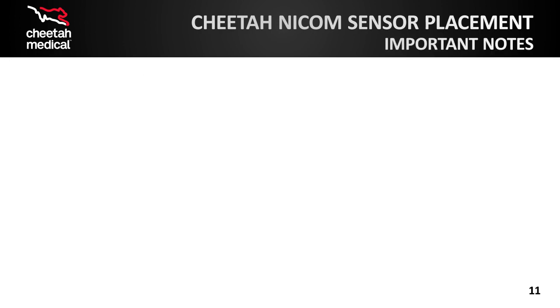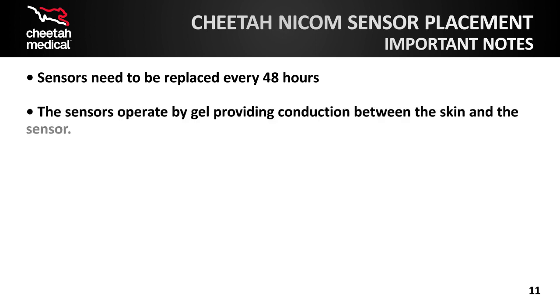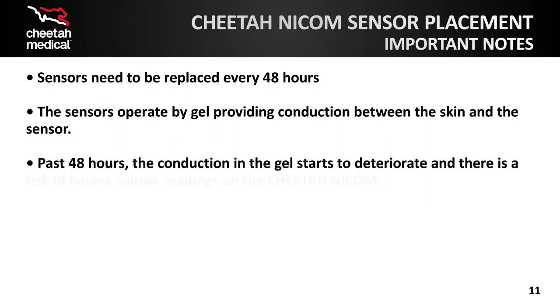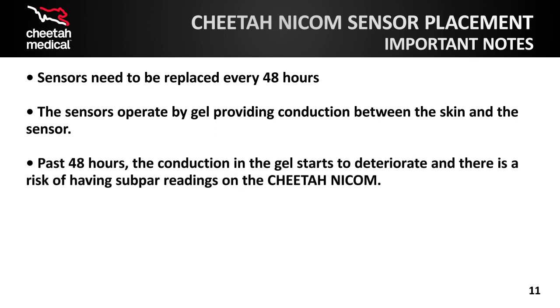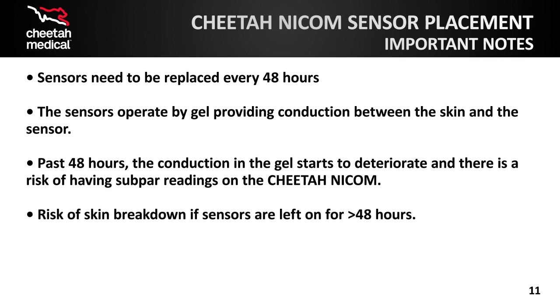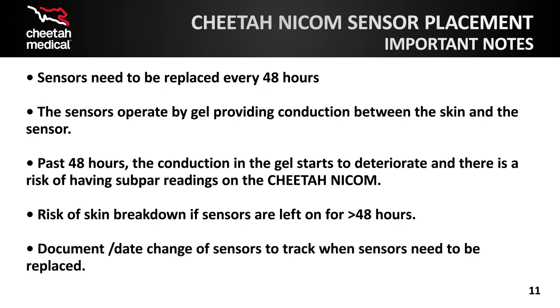There are also important tips regarding adequate sensor placement, replacement, and maintenance to keep in mind. Sensors need to be replaced every 48 hours. The sensors operate by gel, providing conduction between the skin and the sensor. Past 48 hours, the conduction in the gel starts to deteriorate, and there is a risk of having subpar readings on the NICOM. There is also a risk of skin breakdown if sensors are left on for greater than 48 hours. Also, be sure to document the date and time of changing of sensors to track when sensors need to be replaced.